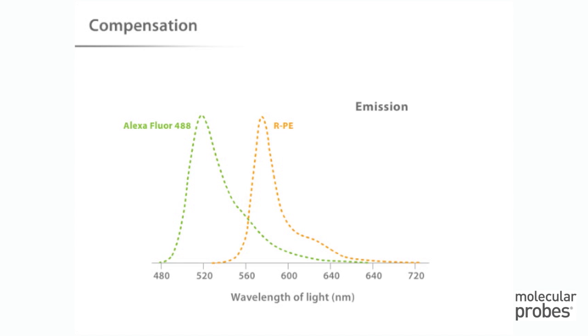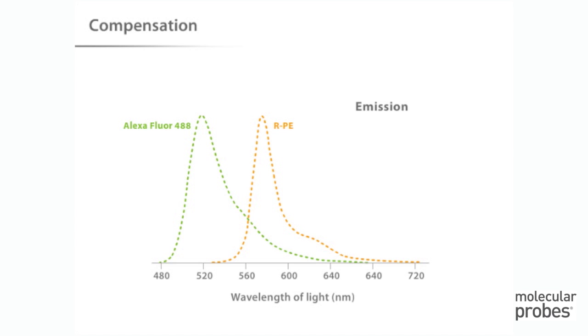For proper interpretation of the data collected, we need to be sure that the fluorescent light we are recording for Alexa Fluor 488 dye is coming from the Alexa Fluor dye and not from RPE, which happens to emit some light in the same wavelength range. To accurately record the fluorescence signal for a given fluorophore, we need to correct the emission signal, and this correction is often called compensation. The flow cytometer records fluorescence using an emission filter chosen to collect the maximum amount of light coming from the fluorophore of interest, and to exclude as much light as possible from other nearby fluorophores.